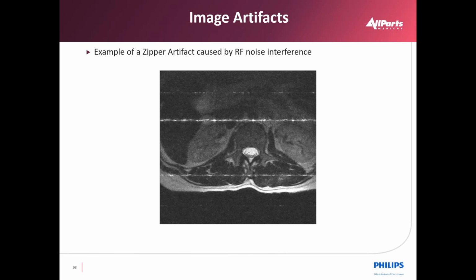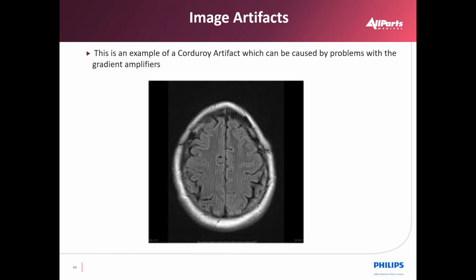This is an example of a zipper artifact caused by RF noise interference. This external interference can be caused by RF leaking into the scan room through defective room shielding at frequencies that are similar to the system frequency. This is an example of a corduroy artifact which can be caused by problems with the gradient amplifiers. They are usually seen as wavy lines in the background of the image and continuing through the entire image.